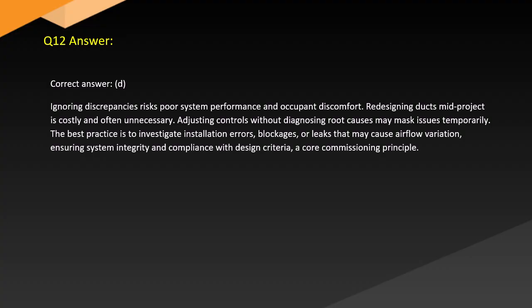Answer: Ignoring discrepancies risks poor system performance and occupant discomfort. Redesigning ducts mid-project is costly and often unnecessary. Adjusting controls without diagnosing root causes may mask issues temporarily. The best practice is to investigate installation errors, blockages, or leaks that may cause airflow variation, ensuring system integrity and compliance with design criteria, a core commissioning principle.